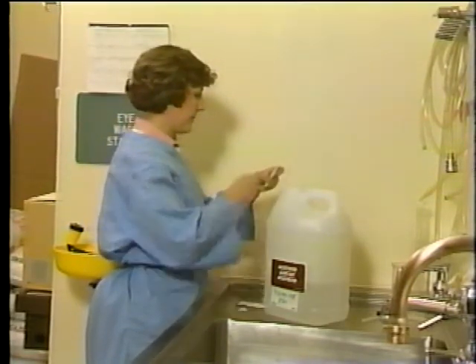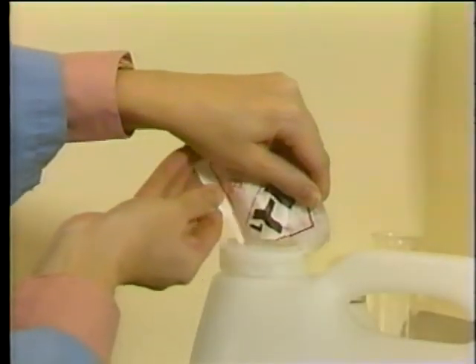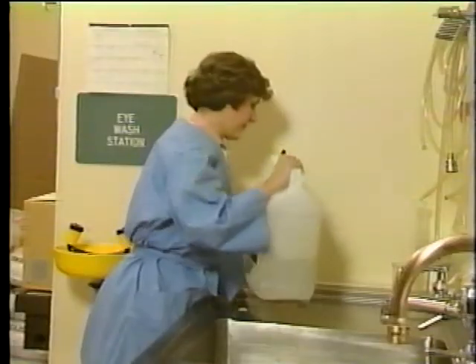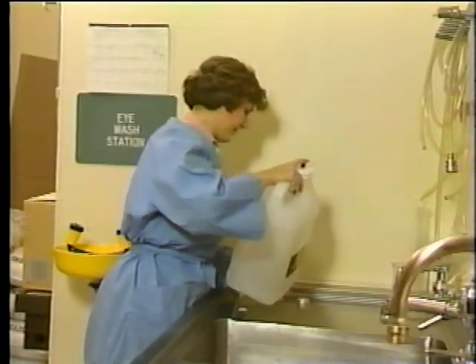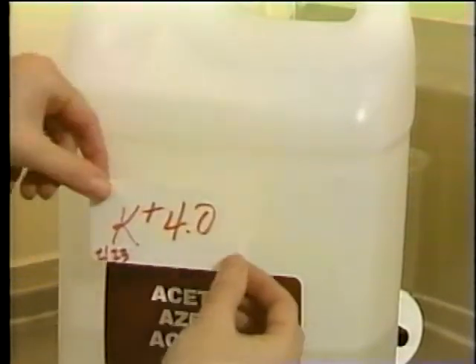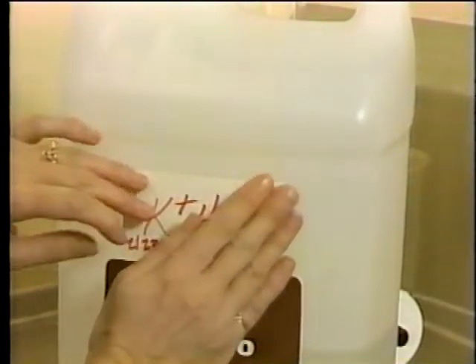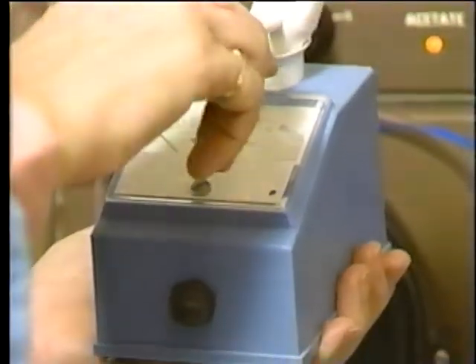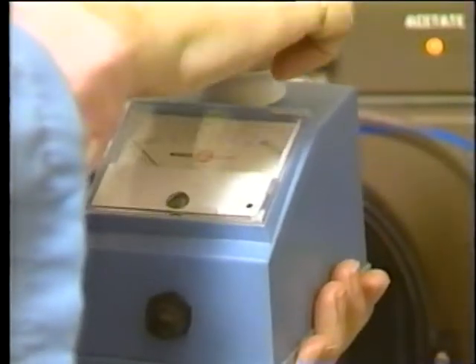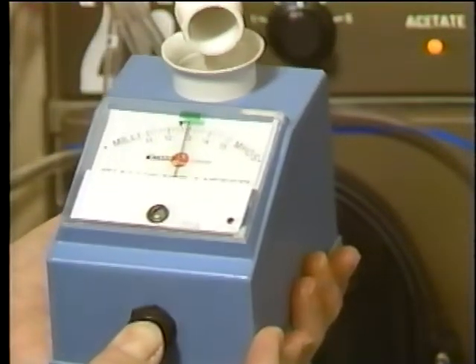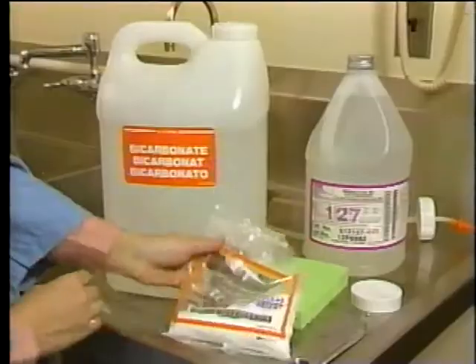Additives must be carefully measured and well mixed into the concentrate before initiating dialysis. Containers must be clearly marked to show additives. When the composition of the dialysate has been altered, conductivity must be re-verified.